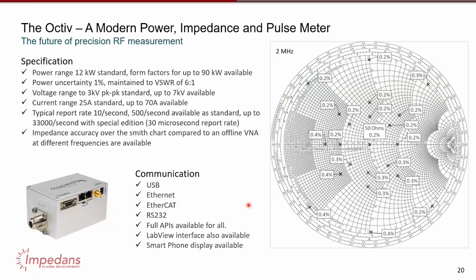I have just 2 slides on the Octiv sensor that we have, but just again to mention that with a VI probe, you're no longer restricted to just getting good measurements in 50 ohms. You can get power measurements over the entire area of a Smith chart for all sorts of complex impedances. And you can get these impedance measurements at real powers, like, if you run at several kilowatts or tens of kilowatts, you can really characterize your matchbox or check your generator at these sort of powers.